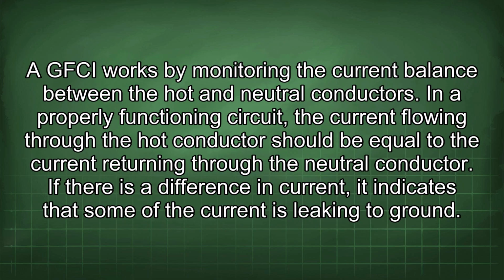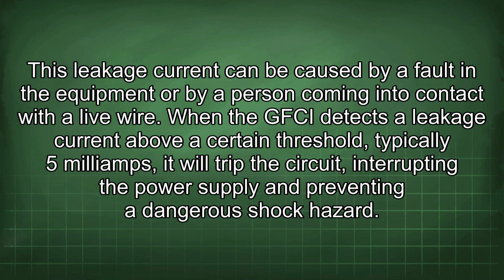A GFCI works by monitoring the current balance between the hot and neutral conductors. In a properly functioning circuit, the current flowing through the hot conductor should be equal to the current returning through the neutral conductor. If there is a difference in current, it indicates that some of the current is leaking to ground. This leakage current can be caused by a fault in the equipment or by a person coming into contact with a live wire. When the GFCI detects a leakage current above a certain threshold, typically 5 mA, it will trip the circuit, interrupting the power supply and preventing a dangerous shock hazard.